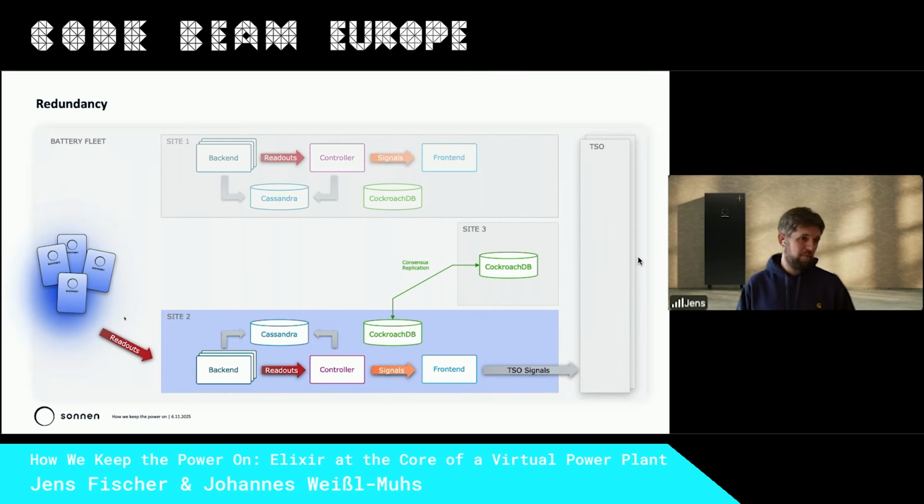The batteries were connected 50-50 to both sides. If side 1 is not reachable anymore, this does not work, of course. So they are migrated by reconnecting, and after a short while we choose the other side as the side to connect to. But one of the advantages of 50-50 connection to both sides is that in the case of a failover, we immediately have 50% locally connected.